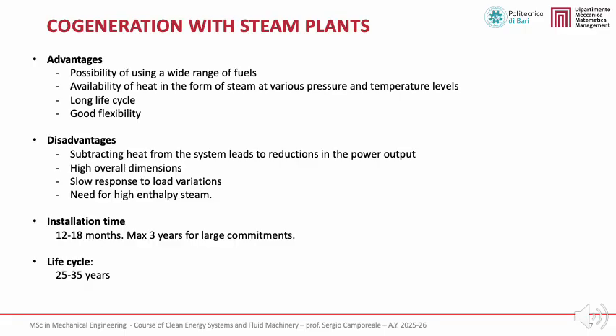On the other hand, steam CHP plants are characterized by large dimensions and slow response to load variations, and electrical output decreases when heat is extracted for cogeneration. For these reasons, they are best applied where thermal demand is stable and continuous and where long operating hours can be ensured, allowing high efficiency and significant primary energy savings in accordance with EU CHP guidelines.